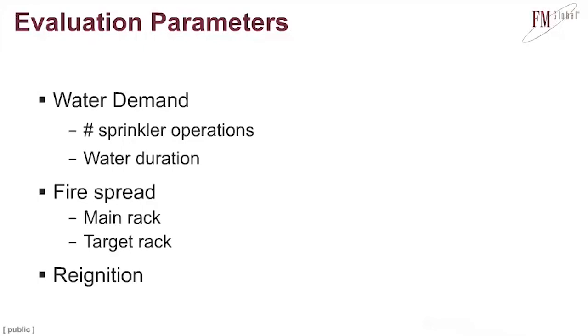Okay, so before we get into this peak fire size, I want to talk about some of the evaluation parameters. Now there's 3 big ones for this test. The first is the water demand. Certainly a major outcome for any fire test is protection guidance, and part of that is understanding how much water you would need in the protection system. And that's done 2 ways. The first is the number of sprinkler operations. So we would take the number of sprinklers that operate in this test, and you apply a safety factor, and then that's going to be what you typically see in a fire protection code. Water duration is also an important aspect.